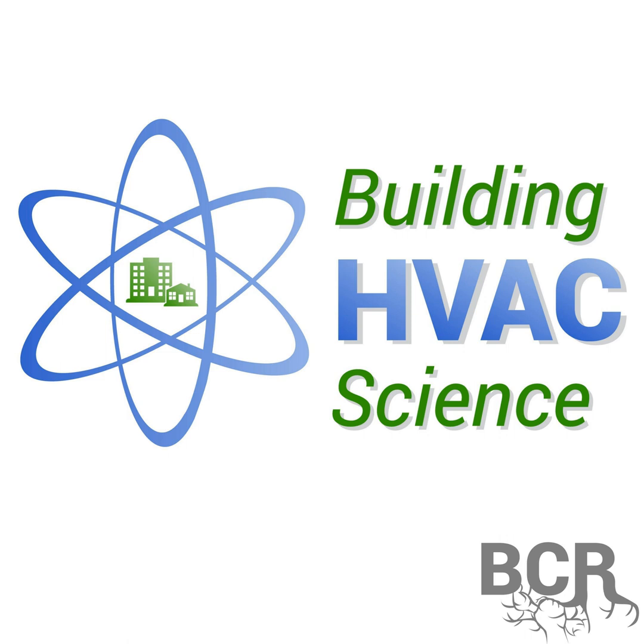And then with that airflow, we can select a filter that gives us that great filtration with very low pressure drop. So let's say for a 1 ton system, we're often using a 20 inch by 20 inch by 2 inch deep MERV 13 filter. And at 400 CFM, the pressure drop is in the ballpark of 0.03 to 0.04 inches of water column, which is about 20% of our static pressure budget for what we're working with on our air handlers. Yeah, the system budget. Yeah.